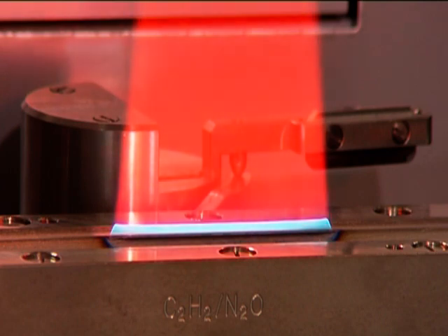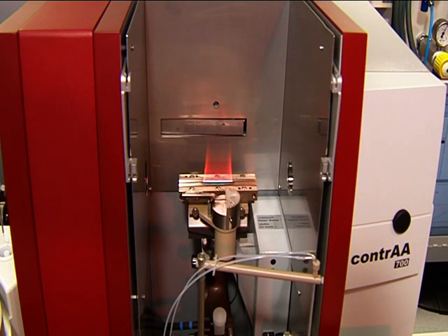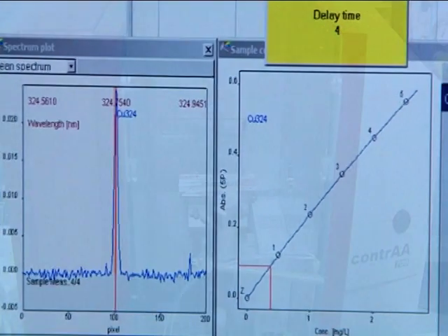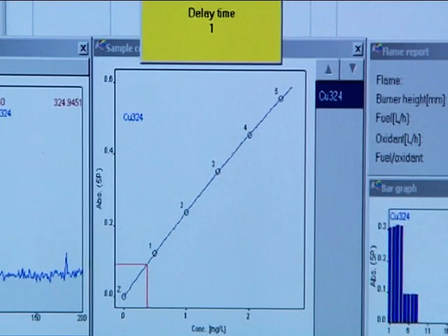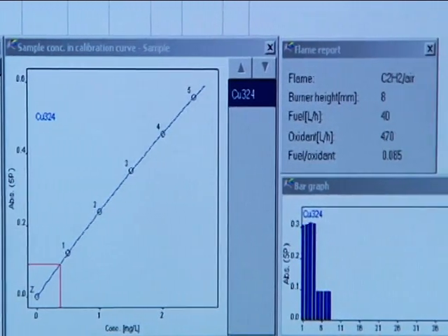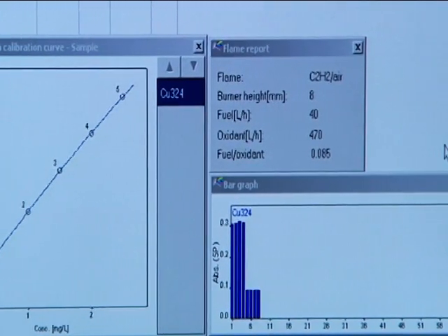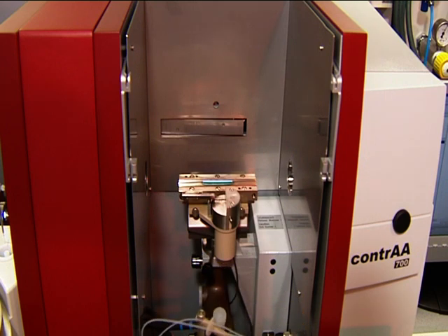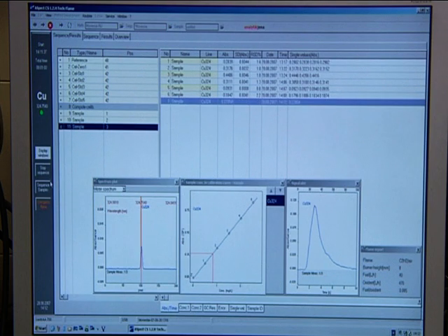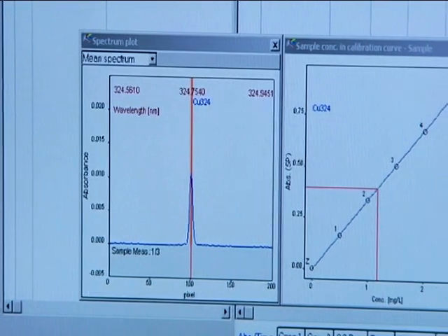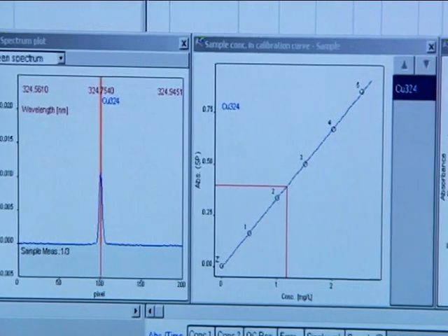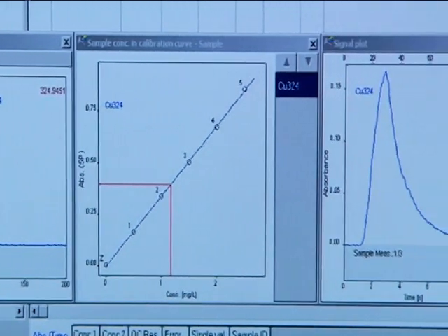An intelligent dilution function automatically dilutes samples which exceed the calibration range by the appropriate factor. Accordingly, subsequent dilutions are a thing of the past. In order to prevent entrainment effects and ensure uniform conditions, the injection switch flushes the system continuously between sample measurements. This is relevant particularly in clinical analyses, but also for difficult samples.